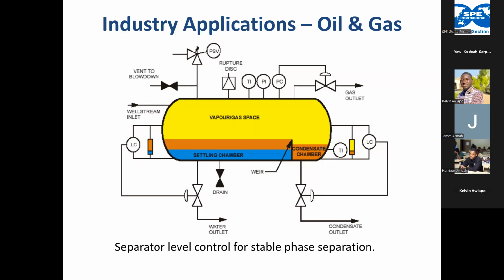Now, let's say the level control on the left side could be set, let's say at 30%, to avoid water from spilling into the condensate chamber. So if the level is going higher, then the valve at the water outlet will open to drain a little of it. And then you also don't want it to go so low that you have oil coming into the water phase. So you put a set point in there, like 30%.